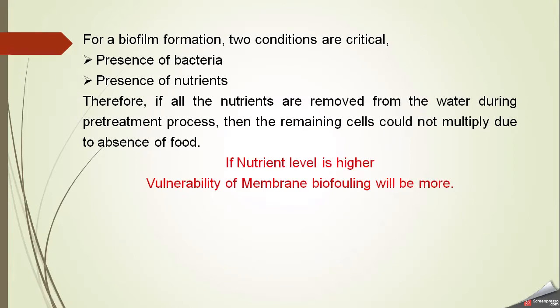Bacteria form a biofilm on the membrane surface. For biofilm formation, two conditions are critical: first, the presence of bacteria that pass through the pre-treatment setup and stop at the membrane; and second, the presence of nutrients, since bacteria need something to eat in order to multiply. If all nutrients are removed from the water during pre-treatment, the remaining cells cannot multiply due to the absence of food.